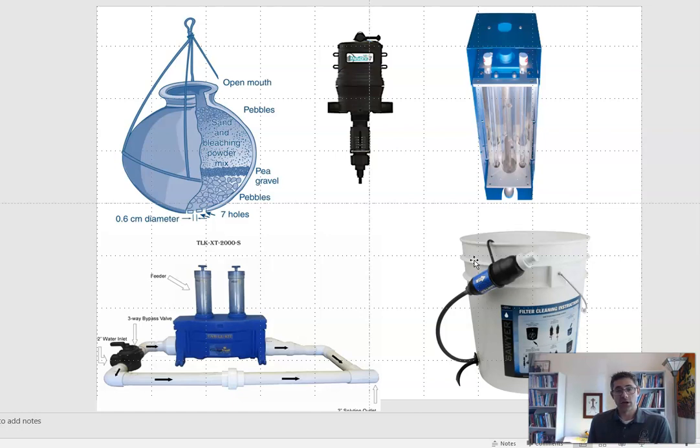Pretty much all bacteria are greater than 0.1 microns in size. They're closer to 1 micron. Now viruses, I think, are around 0.1 micron, and so some of them can maybe still get through here, but a lot of them can't. And so this is not a disinfection technology, it's a filtration technology, but it achieves removal of most disease-causing organisms.